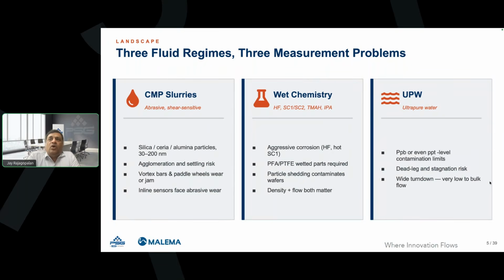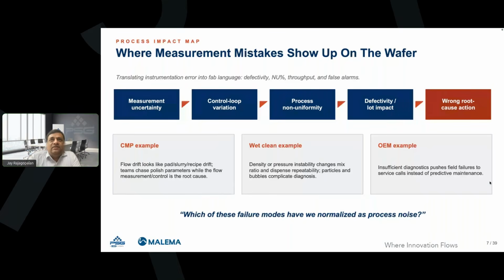In the case of ultra pure water, the contamination limits have drastically tightened. In the past, it used to be just parts per million and parts per billion. Now we are getting into parts per trillion type of detection and limits established. So obviously, that's also a concern that we need to look into. The flow measurement mistakes show up on the wafer, right? So we would wrongly diagnose the problem if it occurs.